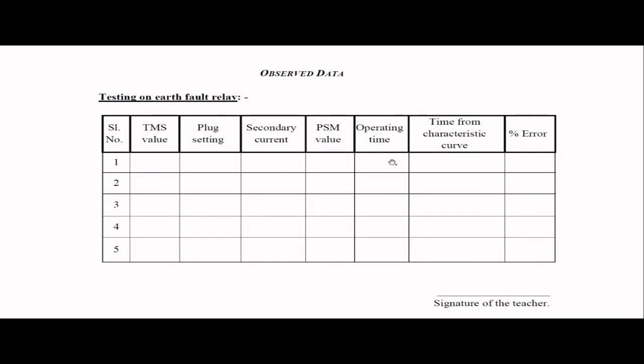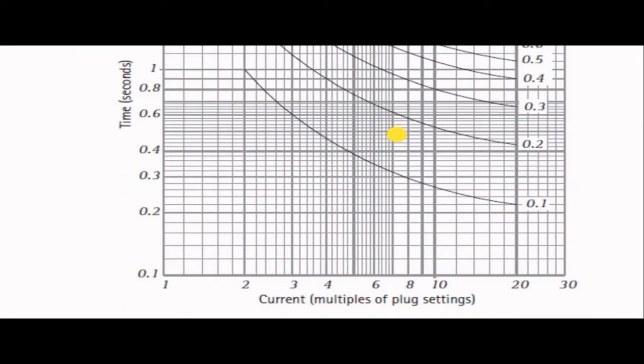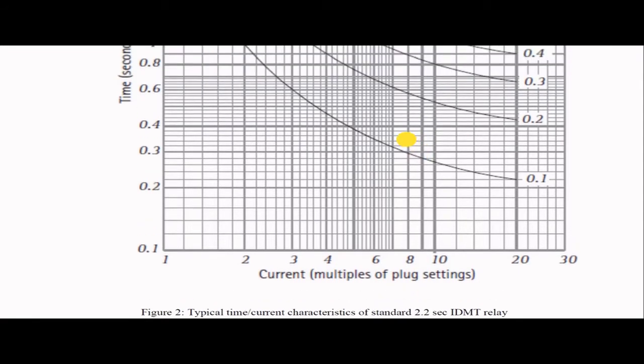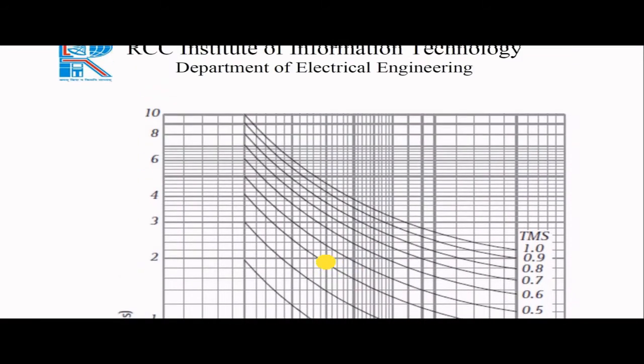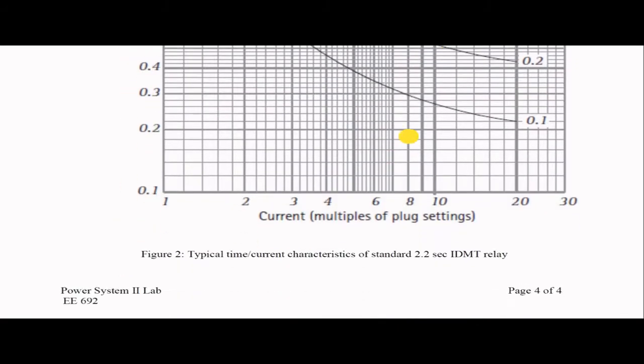Then operating time can be measured directly from the digital timer put on the board, and the time from the characteristic curve. We will definitely discuss another thing which is called the IDMT characteristics curve. From the curve we can get the relay operating time, and our aim is to tally the two readings. That means how much time is actually required and how much time is theoretically required by the relay. So this is our aim. Here you see this is the IDMT characteristics curve, and we'll discuss later on what is the meaning of that IDMT characteristics curve. Okay.